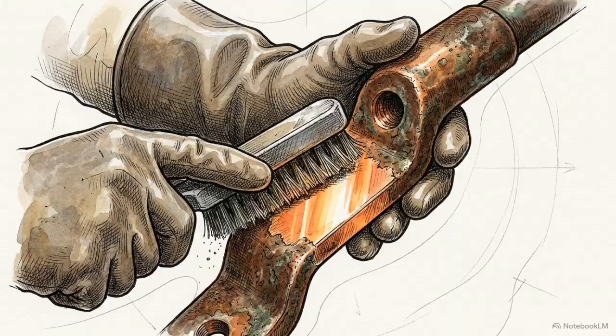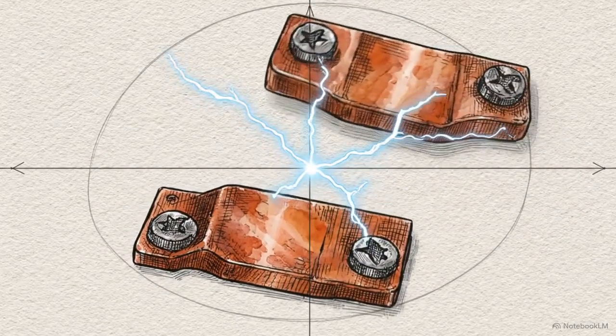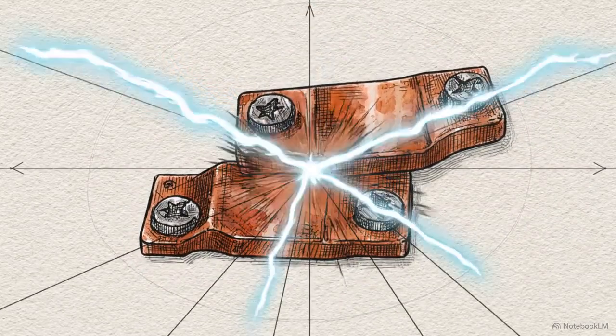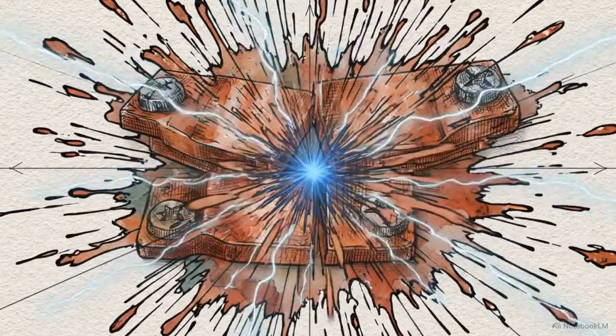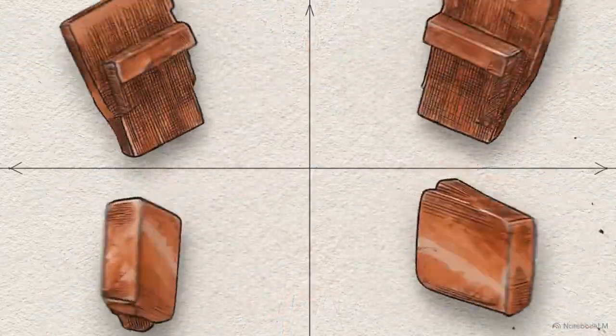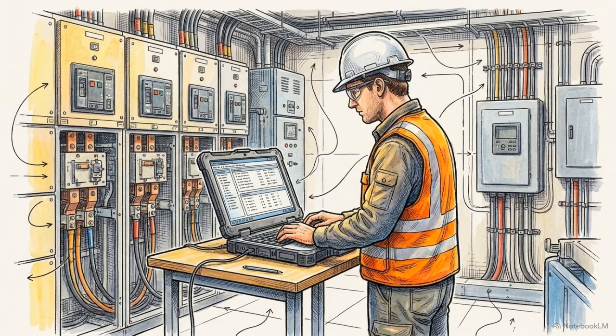If an interlock, like the anti-pump relay, fails to block a reclose, the contacts will continuously cycle and strike against each other under fault conditions. The commissioning engineer ensures system reliability by rigorously diagnosing and documenting these deviations.